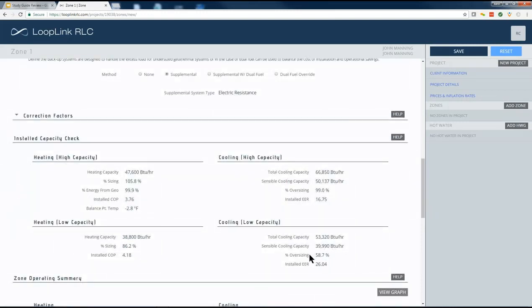But looking at the cooling side here, I assume you guys have probably talked about cooling sizing strategies. Generally speaking, you'd like to see this percent oversizing in sensible cooling capacity relative to sensible load. 25% is kind of the target. Obviously, it's not a make or break deal, but that's optimal, what you're trying to shoot for in terms of percent oversizing. The reason that we choose a dual capacity unit is because then you can check part load capacity, percent oversizing on cooling in an area where our cooling load is much smaller than our heating, and then check the heating sizing in high speed, which is what you're designing for in this case.